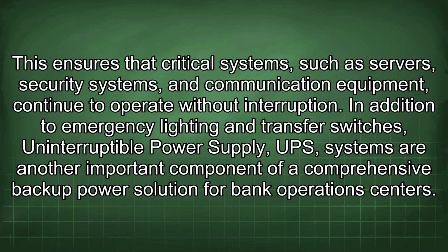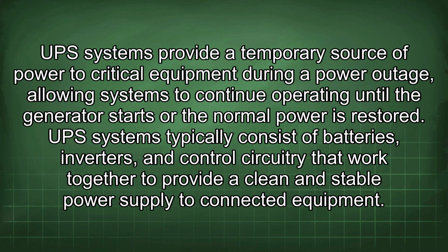In addition to emergency lighting and transfer switches, uninterruptible power supply (UPS) systems are another important component of a comprehensive backup power solution for bank operations centers. UPS systems provide a temporary source of power to critical equipment during a power outage, allowing systems to continue operating until the generator starts or the normal power is restored.